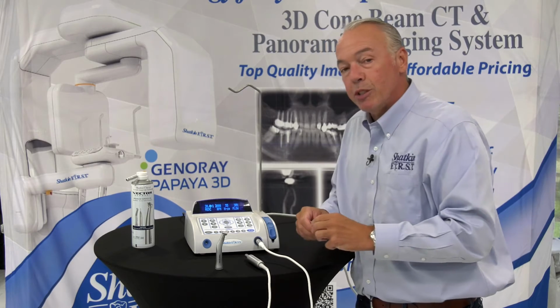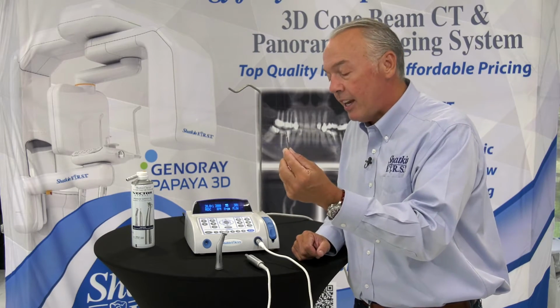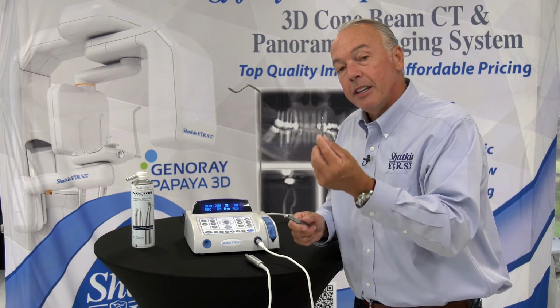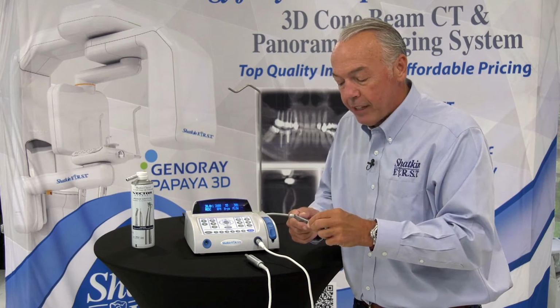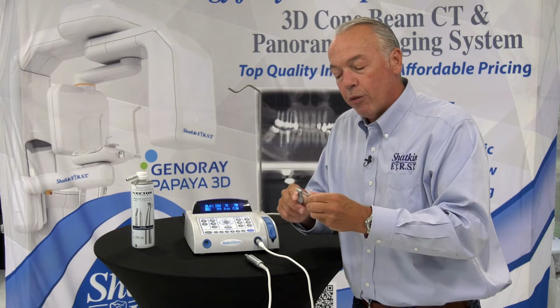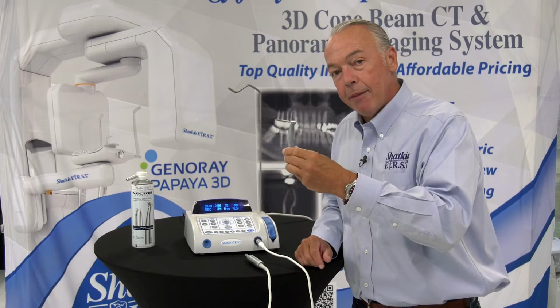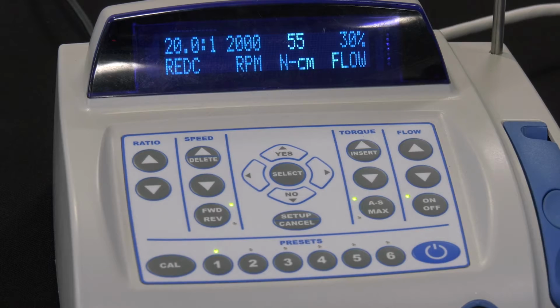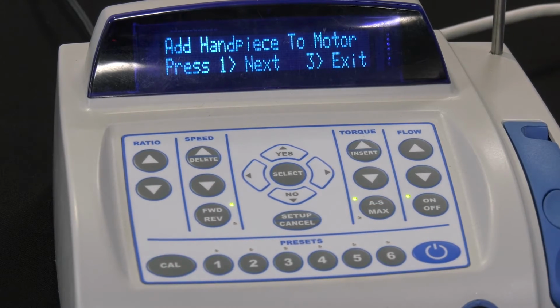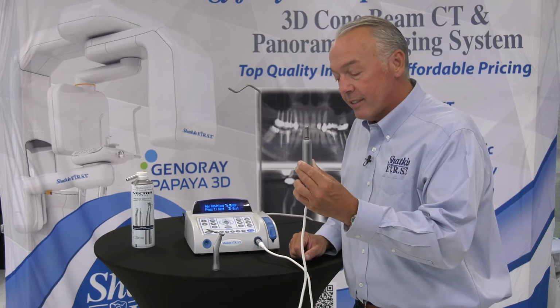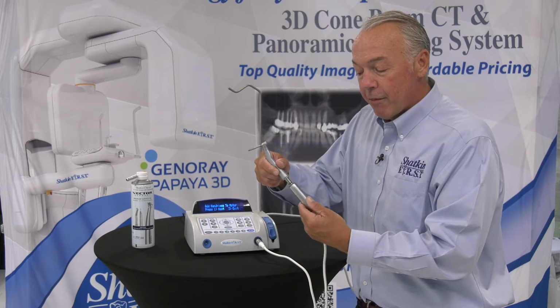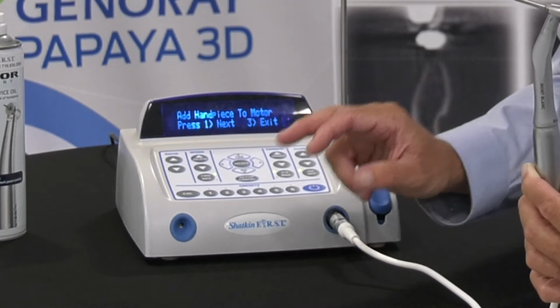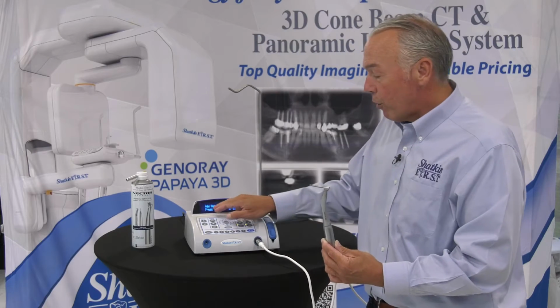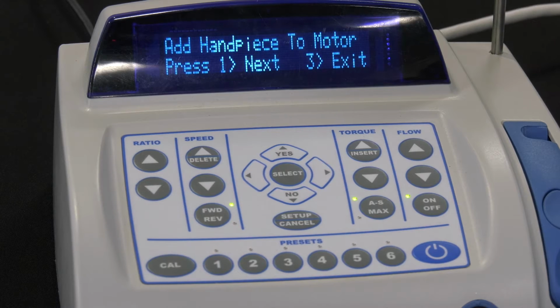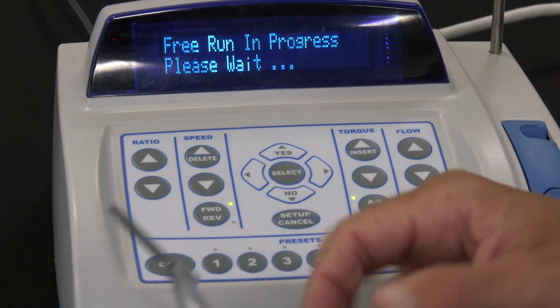The 7000 comes with a dyno pin. So this pin works a lot like your pilot drills, how it fits into the latch handpiece. So you don't have to squeeze the button on the way in, only the way out. So I'm going to put this dyno pin in the handpiece. I'm going to set it right here a moment. And then I'm going to push the calibration button. And on the screen it says, add handpiece to the motor. So this is the motor, and this is the handpiece. I'm adding the handpiece to the motor. I am not putting it in the dynamometer at this point. So number one, add handpiece to motor, which I did. Press 1 for next or 3 for exit. So I'm going to press 1.